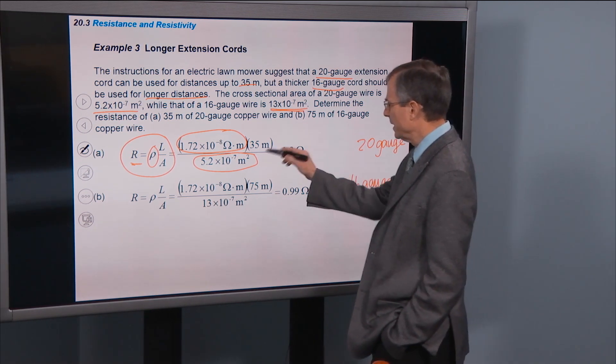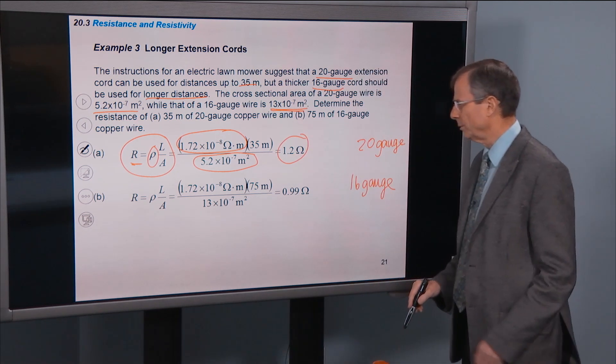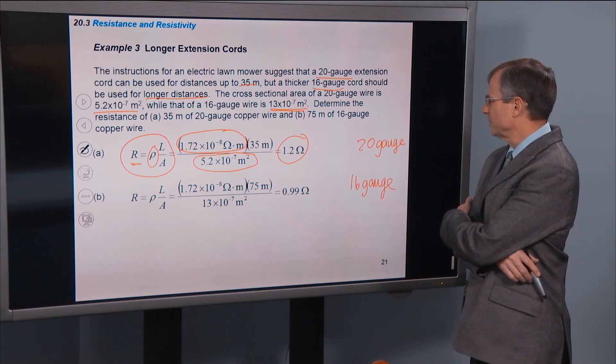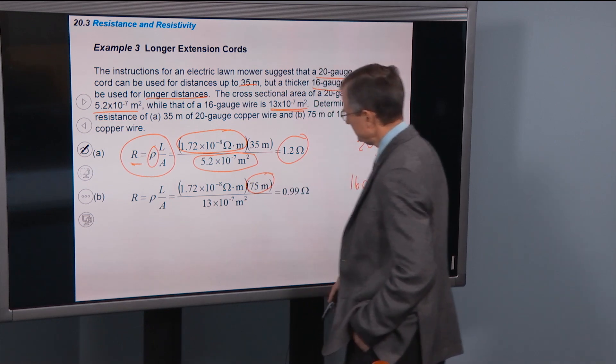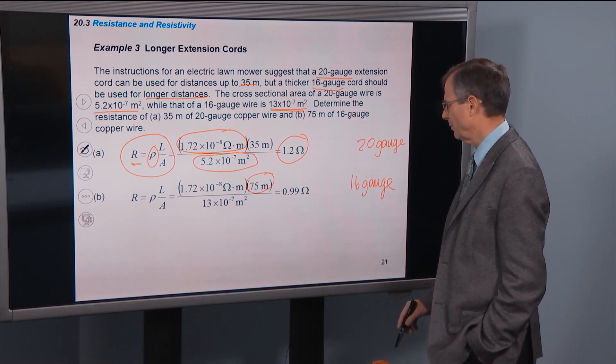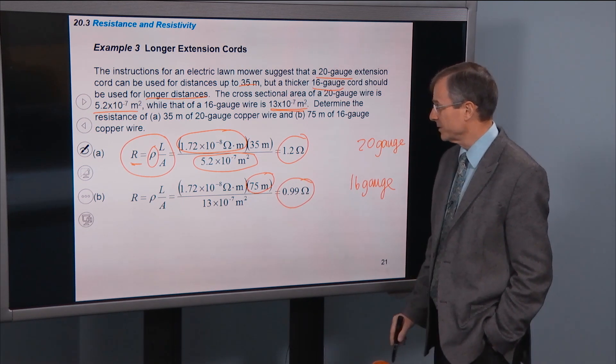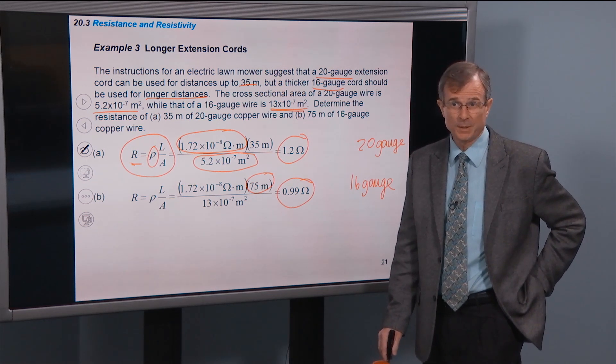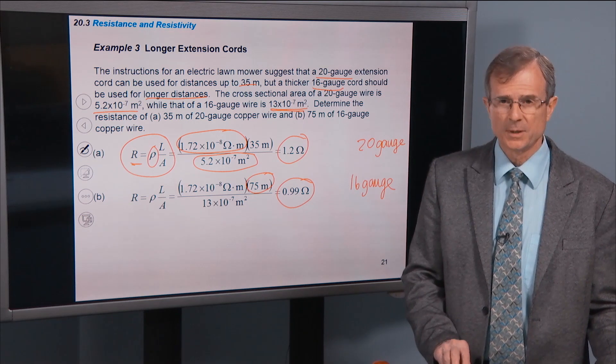So plugging the numbers in for a 35 meter length, you get 1.2 ohms for 35 meters. If you do the calculation for actually 75 meters of this thicker wire, you get a resistance that's even actually less than the resistance for 35 meters of the 20 gauge wire. So that's how you do these kinds of calculations. They're not difficult.